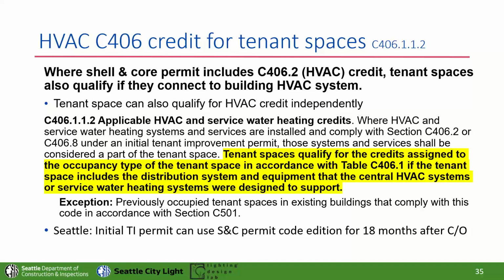No. The interesting thing about TSPR is that it's independent of how great or terrible your building envelope or loads are. It's only saying that for a particular amount of heating or cooling energy your coils are transferring, how efficient are you at doing that? Sometimes you have to go back and spec a more efficient fan, slightly enlarge your duct sizes, or pick a more effective piece of equipment, but something to get you under that line. So the system does seem to be working as required.